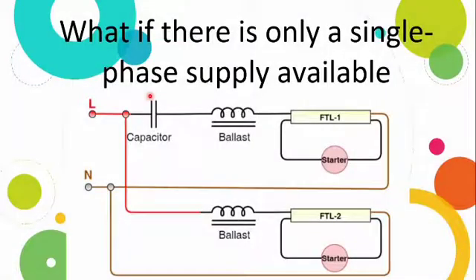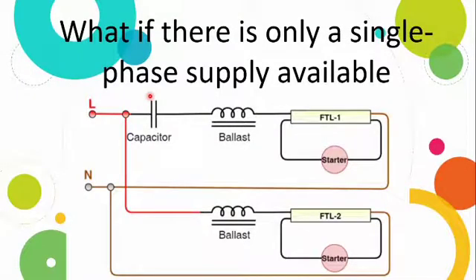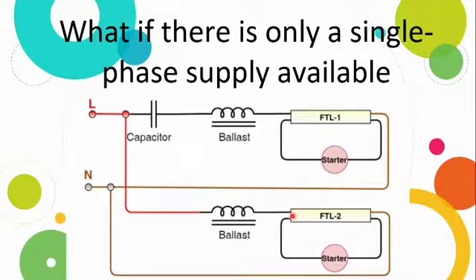The second method: how can we reduce the stroboscopic effect in a single-phase system? We connect an extra lamp — if we use a single-phase system, we can use twin tube lights. When we use twin tube lights in one phase with two lamps, we use the twin tube light diagram. There is a connection called the lead-lag or twin tube light connection. In this connection, we connect a capacitor to one of the lamps.